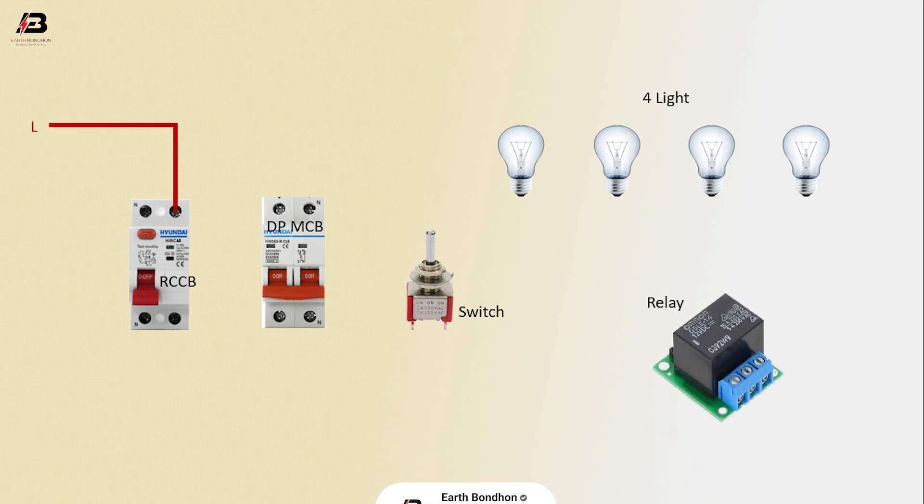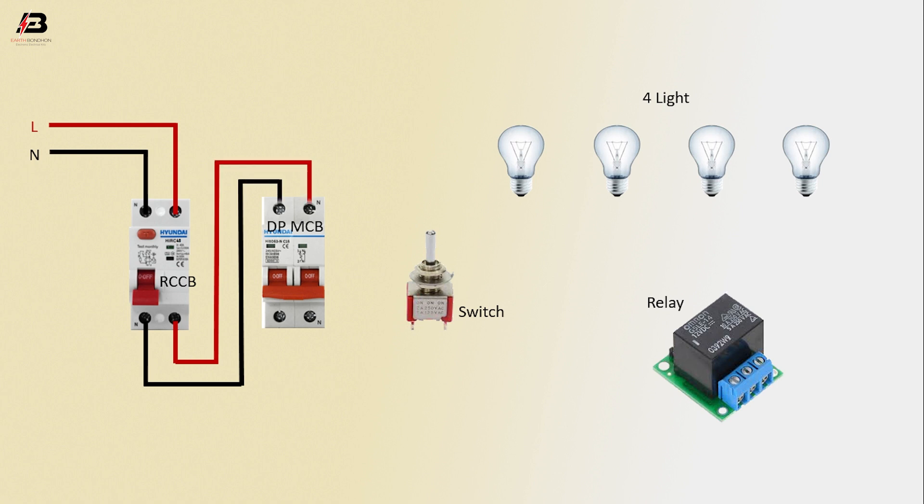Phase connection input to RCCB circuit breaker. Neutral connection input to RCCB circuit breaker. Output connection from RCCB to connect DPMCB. Phase connection from DPMCB to connect switch. Output connection from switch to connect relay.